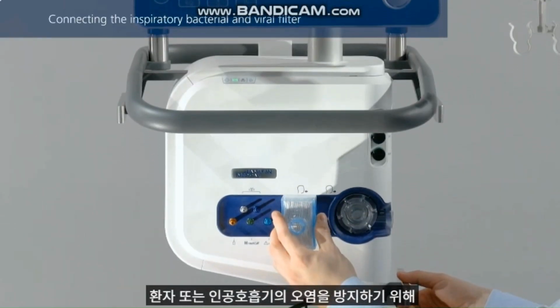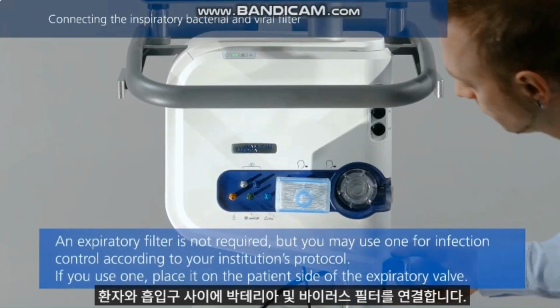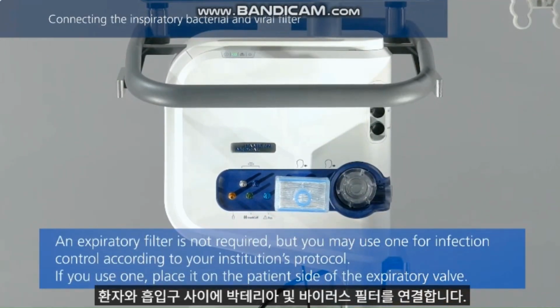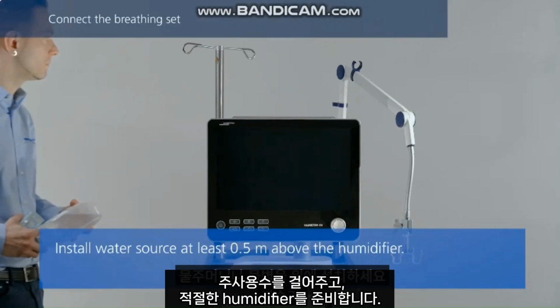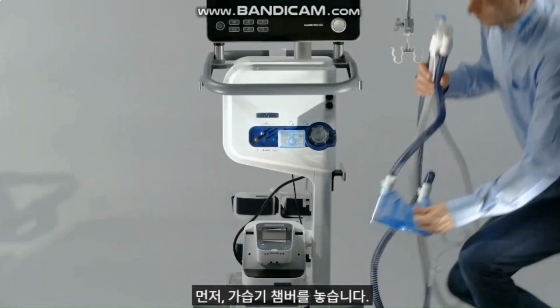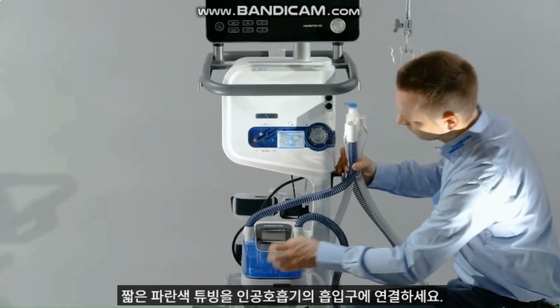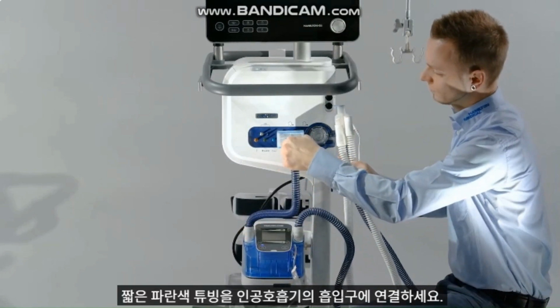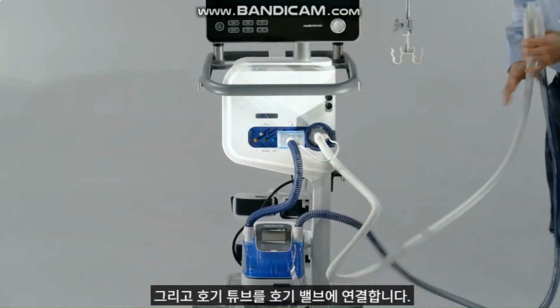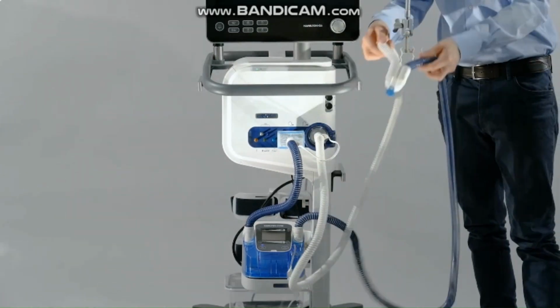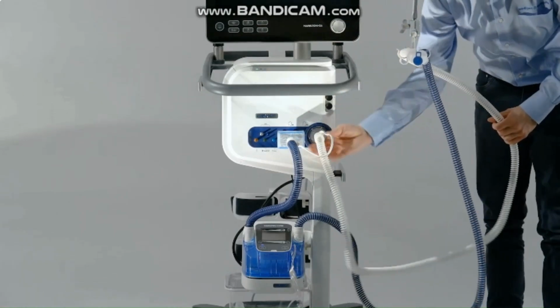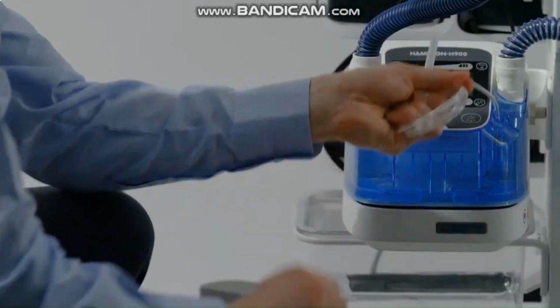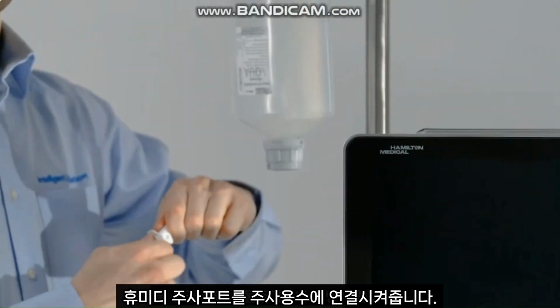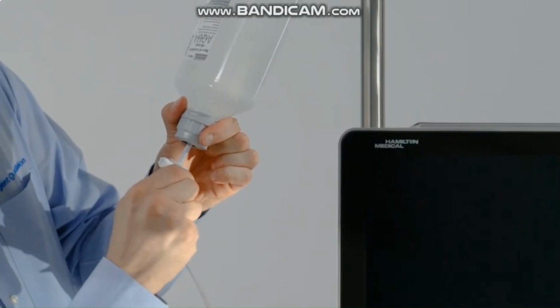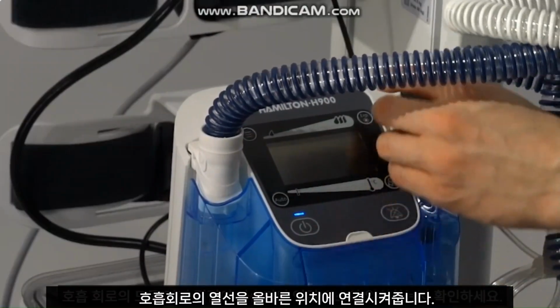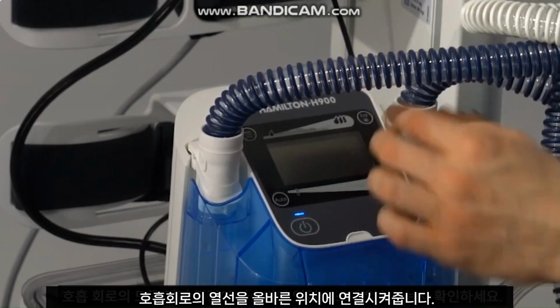To prevent patient or ventilator contamination, connect a bacterial and viral filter between the patient and the inspiratory port. Bottle above the humidifier. First, insert the humidifier chamber. Connect the shorter blue tube to the inspiratory port on the ventilator, and then connect the expiratory tube to the expiratory valve. Insert the water feed line into the water bag or bottle. All electrical contacts on the breathing circuit match the connecting element.